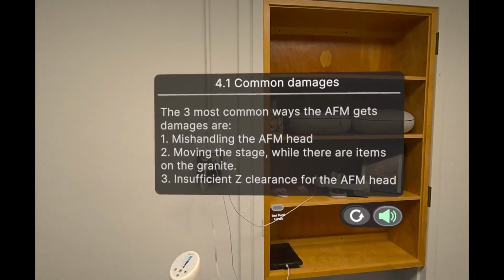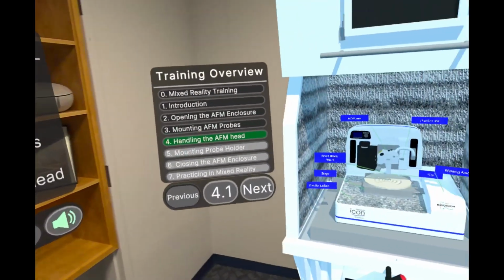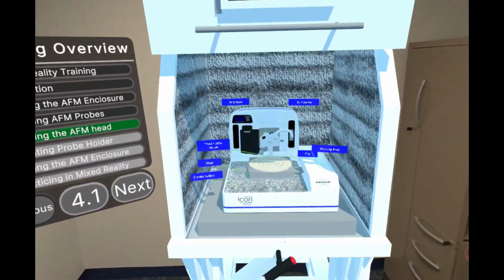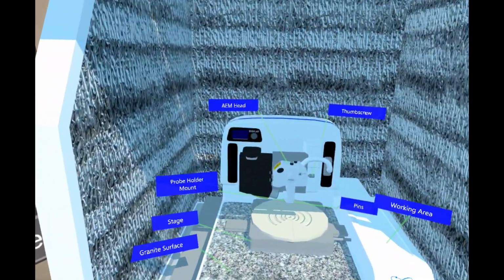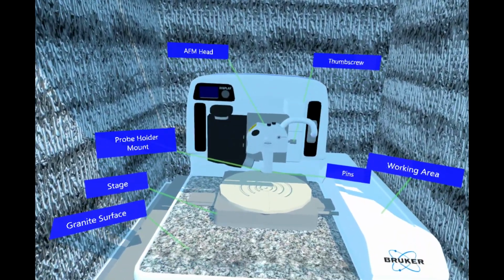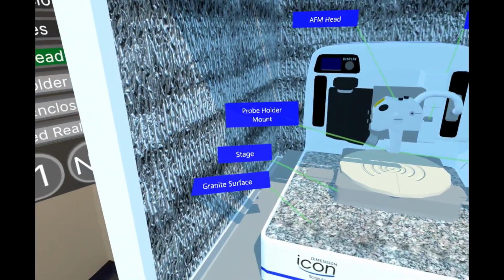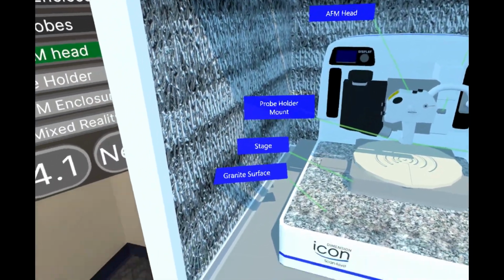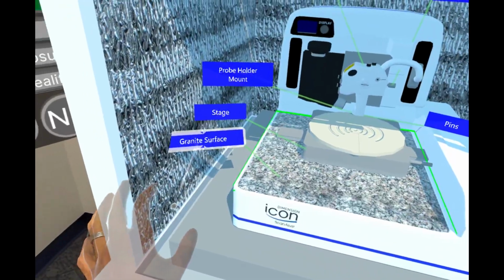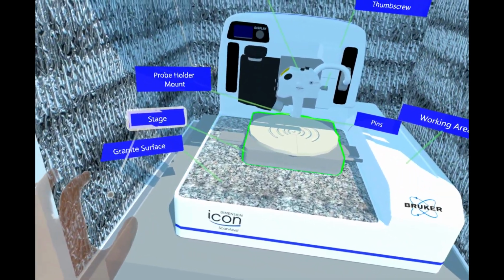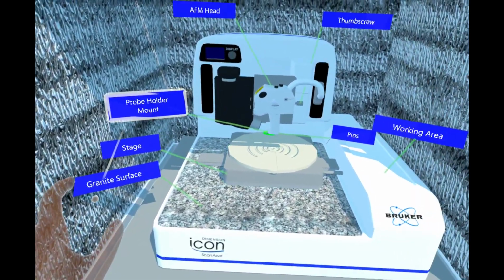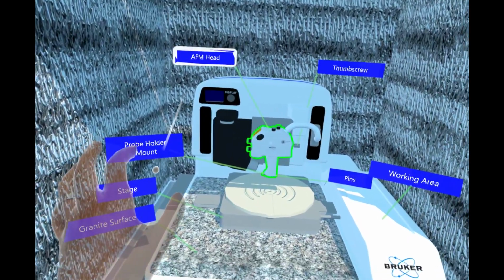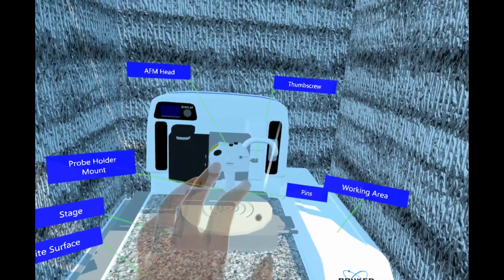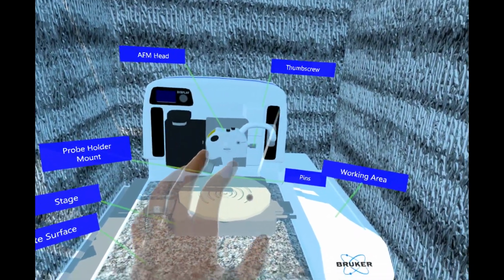It consists of the enclosure, the AFM head, the AFM stage, the AFM optics, the granite base, and the working area on the right side. There are 3 common ways for the system to be damaged by a user: mishandling the AFM head during probe mounting, placing anything on the granite surface and navigating, or navigating in X and Y without enough clearance in Z so the AFM head runs into something.